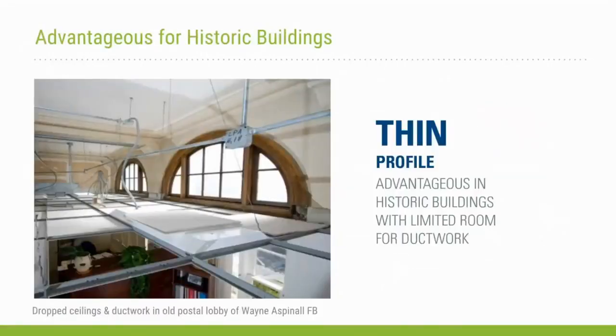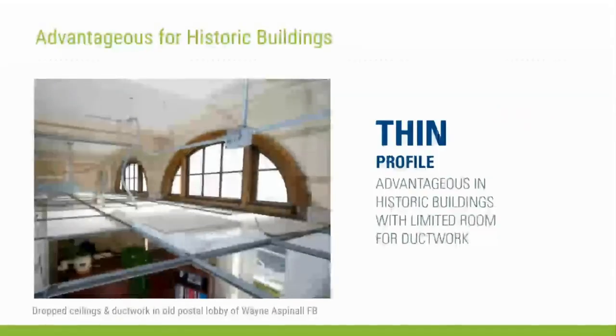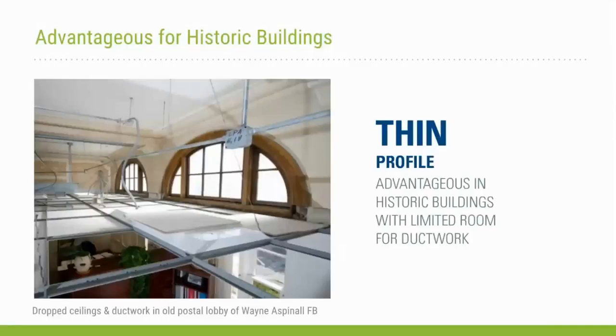Historic buildings can be very good candidates for VRF systems, especially if there's limited space to install or change systems. The primary feature of VRF is that they are less intrusive than other systems. Refrigerant lines are run instead of ductwork, and these require only small holes in walls and ceilings and need minimal clearance between floors. The indoor units can be located in the conditioned space, or there are units available with a low profile for installation above a ceiling. The smaller size of all the components lends to the ease of staging and installing the pieces of the system while minimizing disruption to a building.